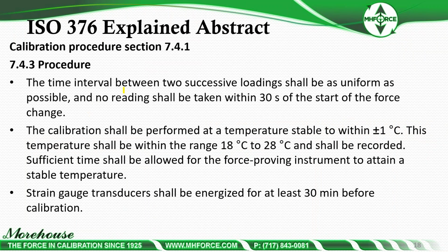So again, time interval. If we look at the time interval between two successive loadings, ISO says it shall be as uniform as possible, and no reading shall be taken within 30 seconds of the start of the force. This is interesting because lots of people using transfer standards or using the automated machines with servo controls and hydraulics, the machine just ramps right up, takes readings, and ramps right down. So to do a calibration with ISO, a lot of times that machine will not be capable of doing that calibration because you actually have to hold the force for at least 30 seconds at each test point.